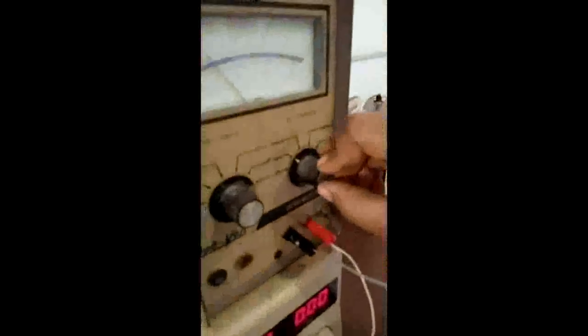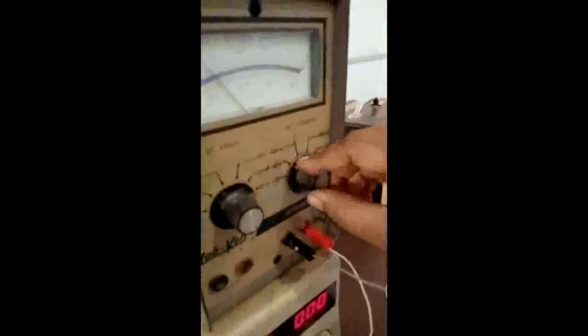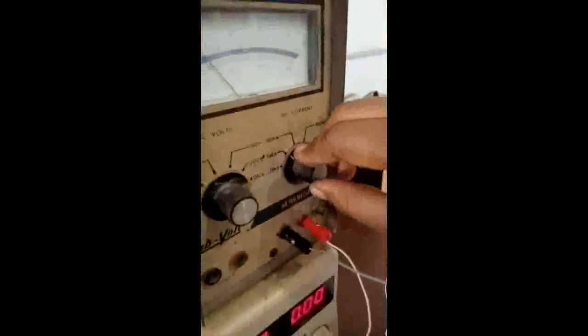Now the range given to us in the manual is 1 milliamp. You can see that I've set the control knob to 1 milliamp. The calibration has to change. You have to convert this. You can choose either the upper scale or the lower scale, but the upper scale is easier to convert than the lower scale.